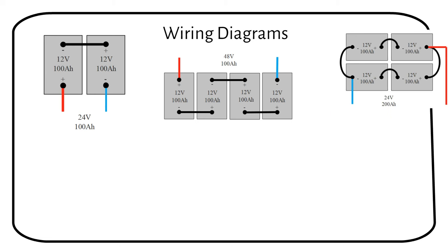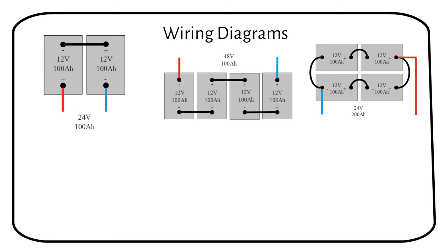We can also use a hybrid connection where we have 2 batteries in series and then in parallel. This is called a 2S2P configuration or series-parallel. We will get a battery of 24 volts at 200 amp hours.